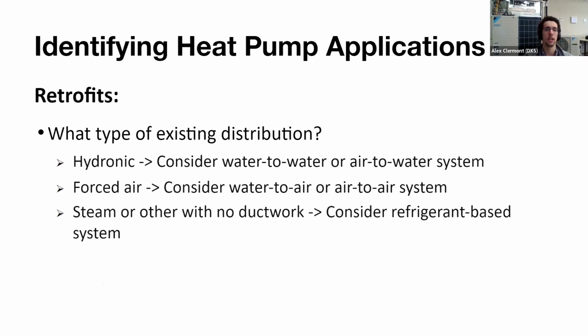Now, in terms of retrofit applications, again, this slide is trying to cover a huge array of different possibilities, but we're trying to simplify it. For example, if you have an existing building with a huge air handler with gas heat, or hot water from a boiler, in that case you'd be forced air, where the option to electrify it is using refrigerant-based systems such as water to air or air to water systems, air to air systems. But again, if you have an existing hydronic distribution loop, there are ways to actually electrify this, as we discussed, using water-cooled or air-cooled chillers, as we talked about a little bit before. Now, if you do have steam in your building, you could do electric baseboard for heating, but usually these buildings only have heating, so you're starting from scratch if you're trying to really add cooling in there.